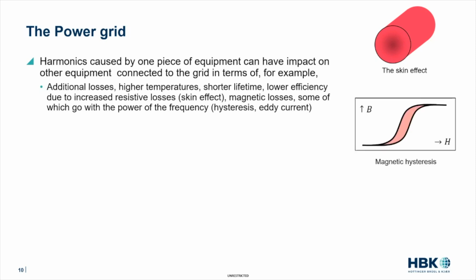A second effect is that you have magnetic losses. If you have magnetic materials in your device, then every time you go through a single cycle of your current, you lose energy because of magnetic properties. Every time you go through such a loop, you lose energy relative to the area of this curve. And of course, if you have a harmonic that has a higher frequency, in a certain time you go more often through this loop. So you lose more energy if you have harmonics. The magnetic losses due to harmonics are proportional to the frequency, so it's getting worse with higher harmonics.